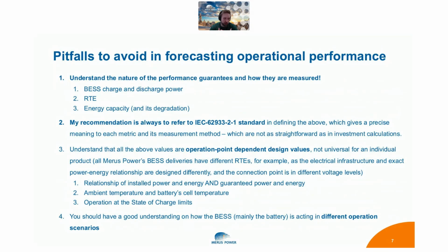First, buyers, sellers, and system integrators need to understand the nature of performance guarantees and how they are measured: charge and discharge power, round-trip efficiency, energy capacity. Many listeners, many people operating in this market, have a good intuitive understanding of these. But if you look at the IEC 62933 standard, which has clear definitions, they are not as intuitive as you might think, and have a very specific way of being measured under standard conditions.